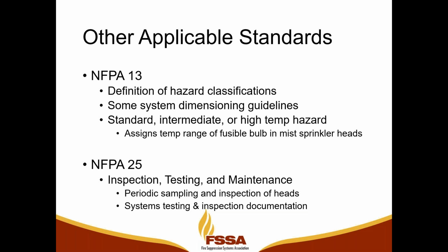When looking at sprinkler heads that are used in water mist type systems, just like in NFPA 13, they do have some designations when using fusible bulbs in the sprinkler heads. You have to meet either standard, intermediate, or high temp hazard classifications, and those are really defined by the temperatures that the bulbs could be exposed to on a regular basis.